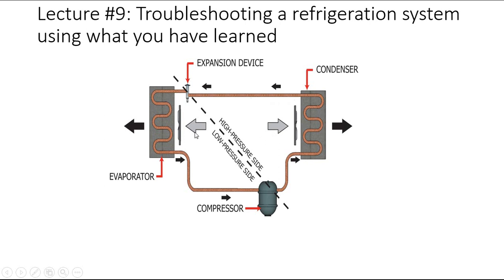Check your filter. Generally all systems—residential, commercial, even automobiles—have a filter on the inlet air of the evaporator. Make sure that filter is clean. If you can see the evaporator, make sure there's no buildup of lint, dirt, or mud. That's really important.